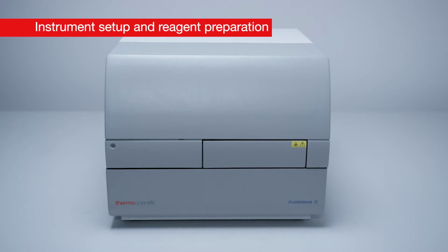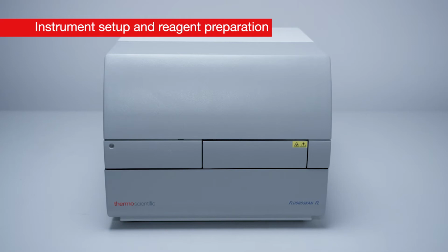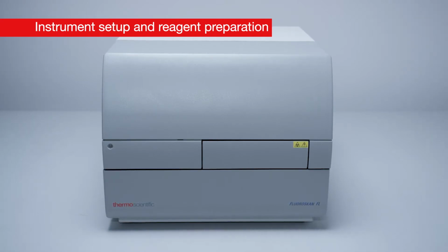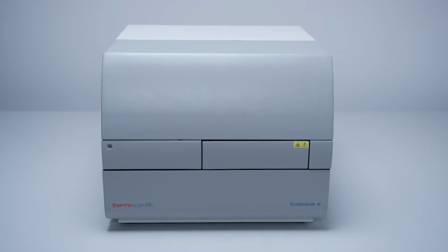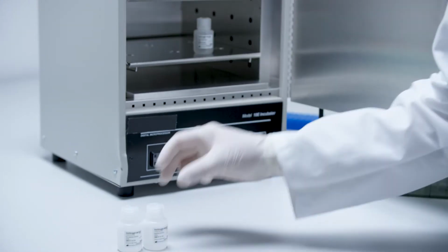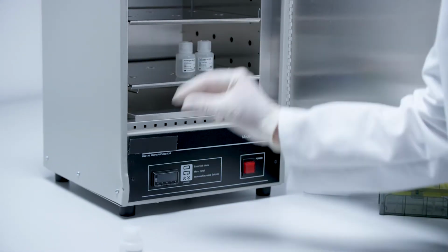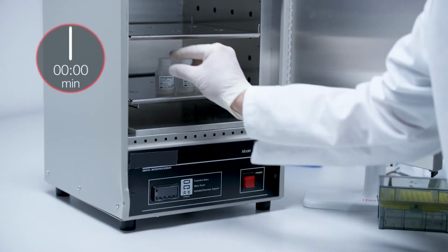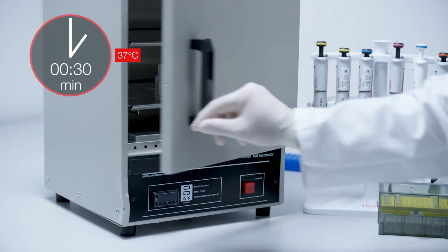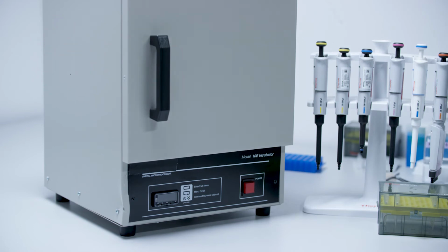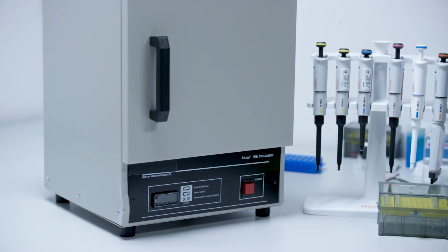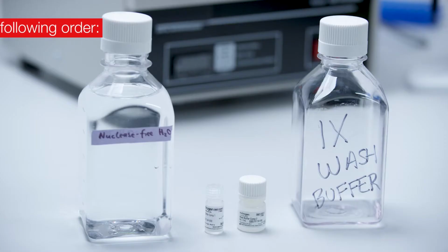Refer to the QuantiGene Singleplex user guide for proper instrument settings, and refer to the multi-mode microplate reader or luminometer user guide for setup and calibration procedure. Warm the pre-amplifier, amplifier, and label probe diluent solutions at 37 degrees Celsius for 30 minutes to dissolve any precipitates. Leave at room temperature until ready for use.